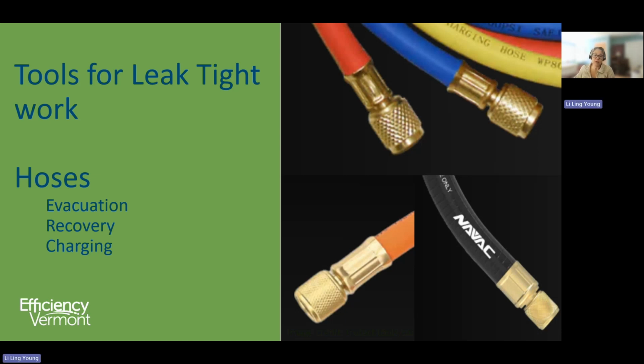Recovery hoses should also be large, but here there's a compromise, so we don't end up with a large volume of stranded refrigerant. A short recovery hose between the recovery machine and the recovery cylinder keeps the hose volume low, and a 3/8" recovery hose makes sure the recovery goes fast. Easy, fast recovery avoids the temptation to vent refrigerant. A 1 or 2 foot 3/8" recovery hose to the tank, any length 3/8" recovery hose from the equipment to the recovery machine. And finally, charging hoses don't need to be large diameter, but they should be dedicated for charging, and they should be pressure rated.